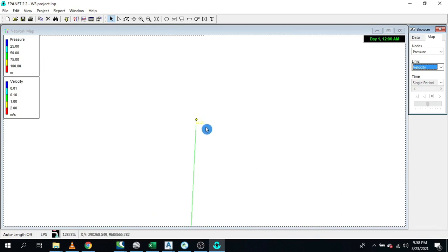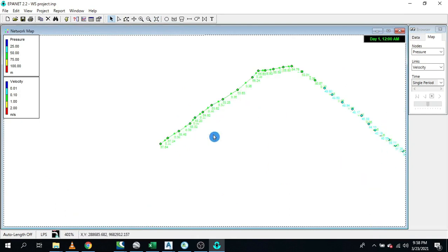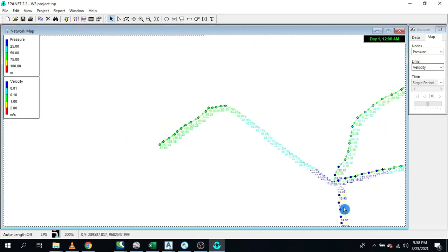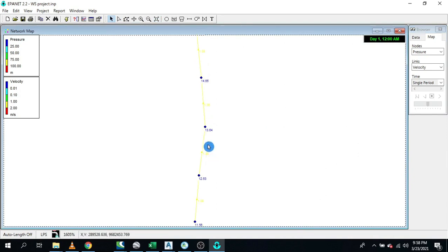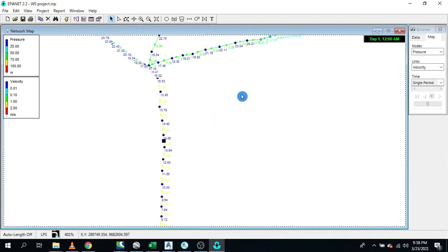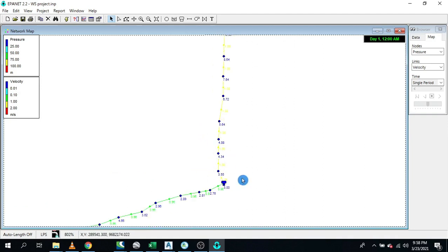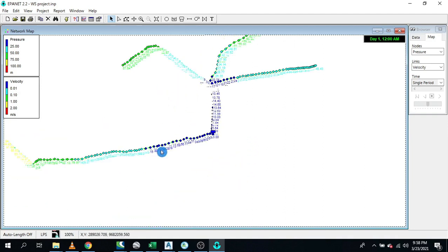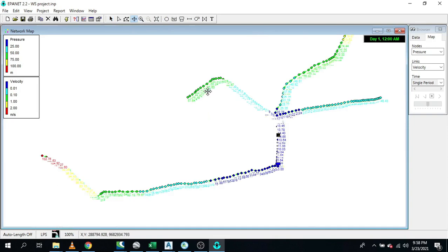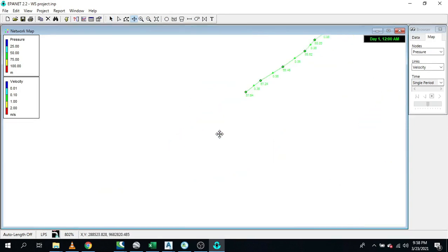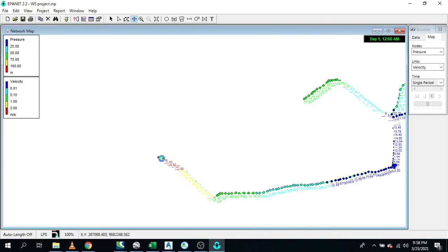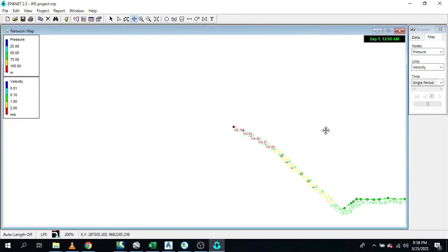So what we need to do next here, the pressure is 82, that is quite big. And at this point here again, flow is how much? As you can see here, we have 1 meter per second. It's not bad, but again, it's not that good. We can increase a little bit here, but there is no need. Let's see. Now at the end here we have like 50. Again, this here is 100, is a little big.